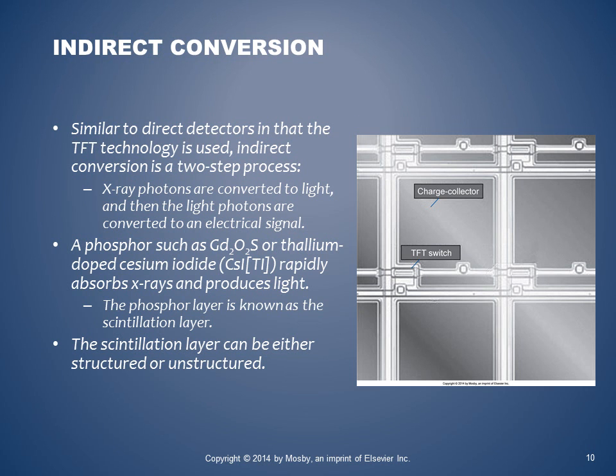Similar to direct detectors in that the TFT technology is used, indirect conversion is a two-step process. X-ray photons are converted to light, and then the light photons are converted to an electronic signal. A phosphor such as Gd2O2S or thallium-doped cesium iodide rapidly absorbs X-rays and produces light. The phosphor layer is known as the scintillation layer.